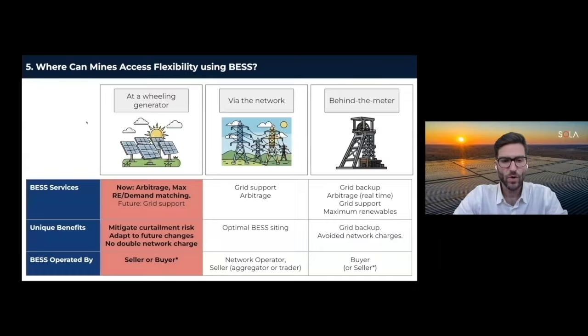There are three different ways that mines can use batteries to achieve that flexibility. You can co-locate it at a wheeling generator. So if you're purchasing energy from a wheeling facility across the network, a battery can be placed at that generator to change the way that generator dispatches into the network for the energy that you are receiving. You can also potentially have a standalone battery without a generator on the network, or you can place a battery at your load point. Each of these approaches has slightly different nuances and benefits.